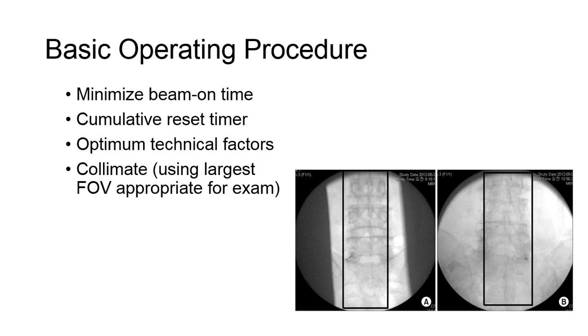You can also make use of the cumulative reset timer. An audible alarm should sound every 5 minutes of fluoro, but you should make sure to track the entire amount of fluoroscopic beam on time for any procedure. Optimum technical factors should be employed, generally using the lowest MA setting and highest KVP appropriate for the fluoroscopic examination.